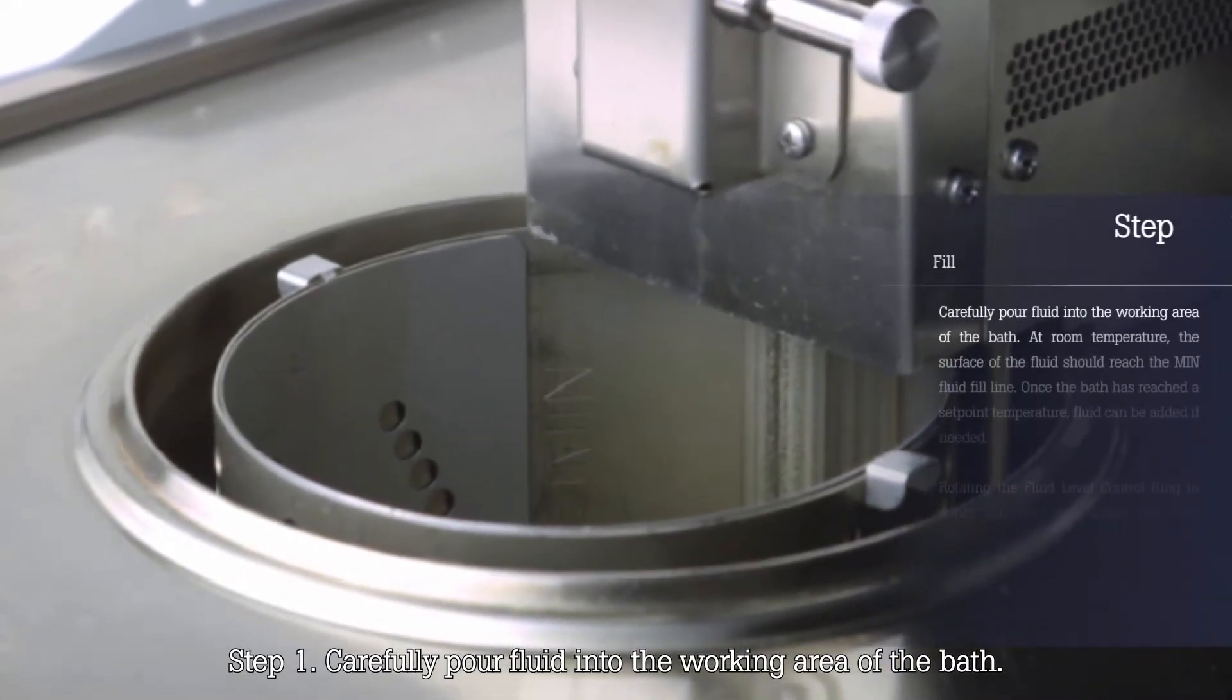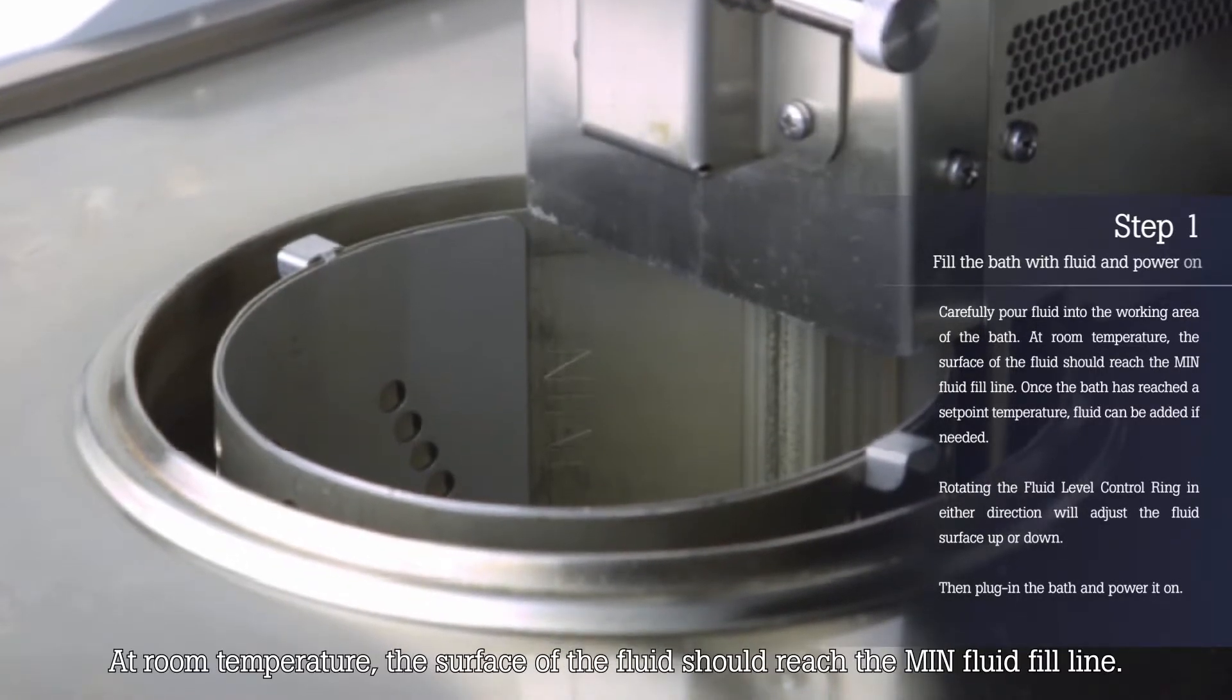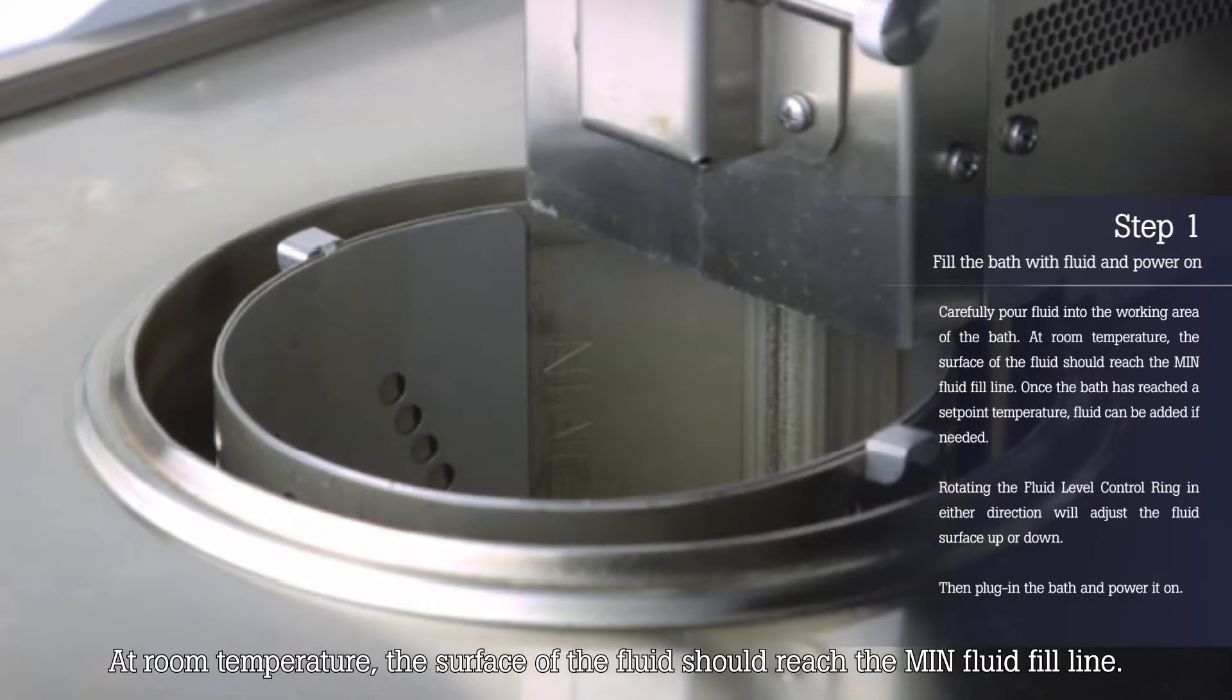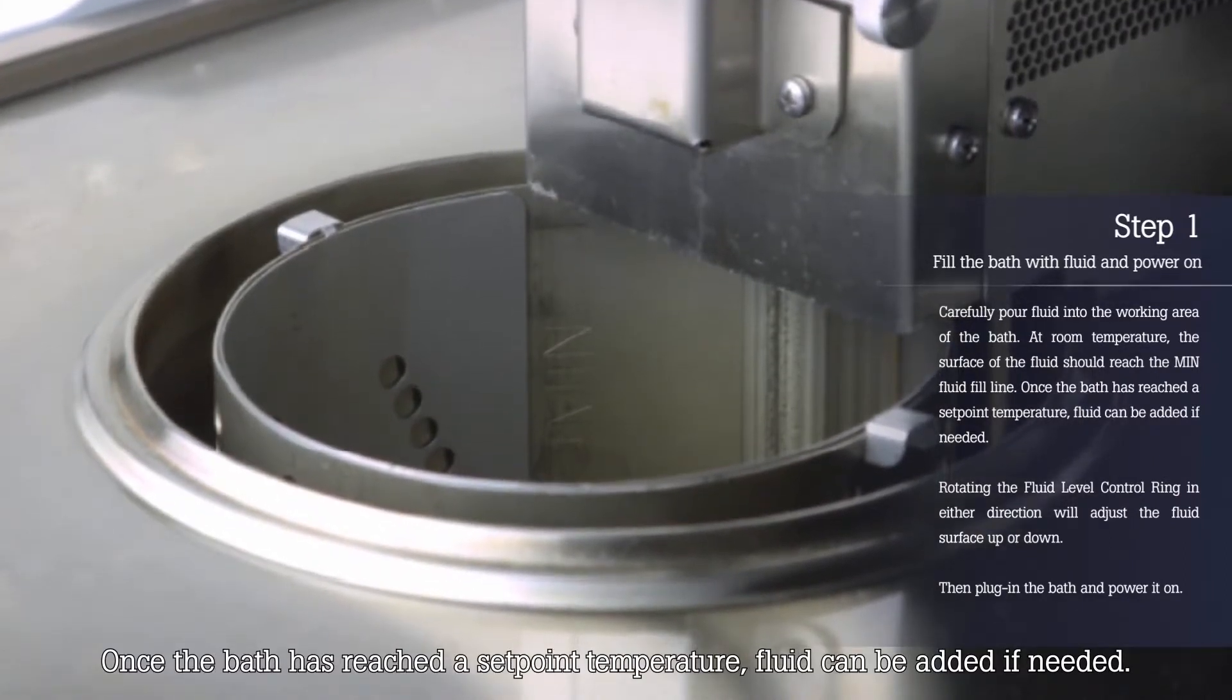Step 1. Carefully pour fluid into the working area of the bath. At room temperature, the surface of the fluid should reach the min fluid fill line. Once the bath has reached a set point temperature, fluid can be added if needed.